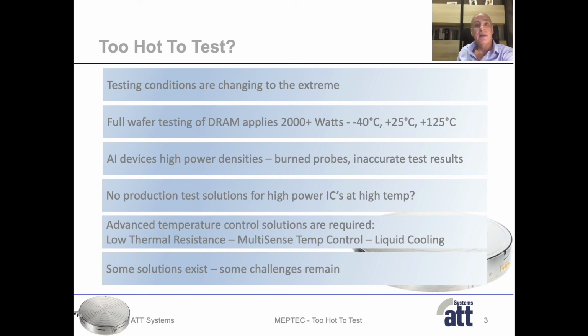AI devices are facing high power densities due to the small die size. This results in high junction temperatures, causing burned probes and inaccurate test results. How can we control the chuck and device temperature at low and high temperatures? Is it too hot to test? For sure, it's getting more challenging to control the chuck and the device temperatures. Therefore, advanced thermal systems need to have low thermal resistance, active temperature control with a smart arrangement of control sensors, and high cooling capacity through liquid-cooled chillers. In other words, active temperature control is crucial, and the thermal system is an integral part of the test cell.